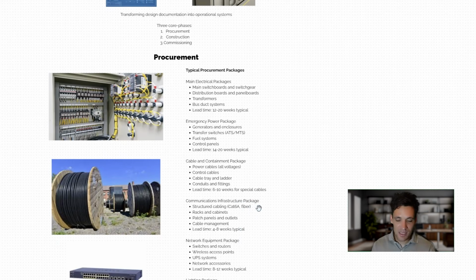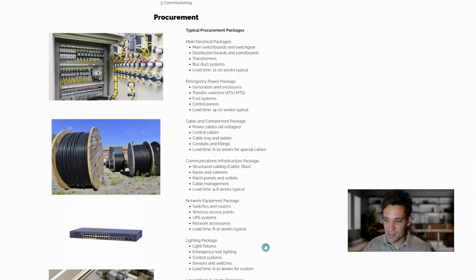So typically, power cables, you'll order the larger cables from the cable schedule that have a long lead time from a single supplier, and you might order all the smaller circuit cables as you need them from a local wholesaler. Cable tray, no matter how good the 3D models are, it's always tough to accurately order cable tray. So typically the bends take more time to come than straight sections. So you typically order bends from the model with some allowances, and then order all of the longer straight sections and top them up as you need them so you don't end up with too much wastage.